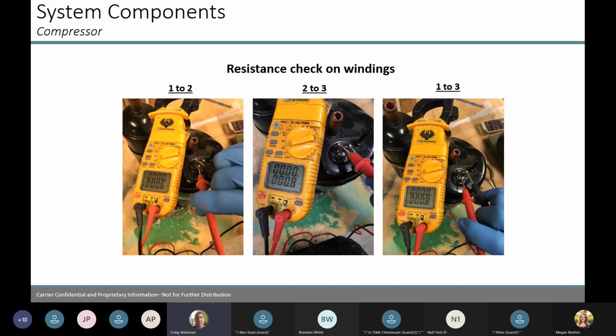We changed the motor. Guy puts it in, the brand new motor is not working. The wire pulled out. Once we pushed it back in, everything ran 100%. So always test at the board and always test at whatever you're testing, and make sure the wires are pushed in.